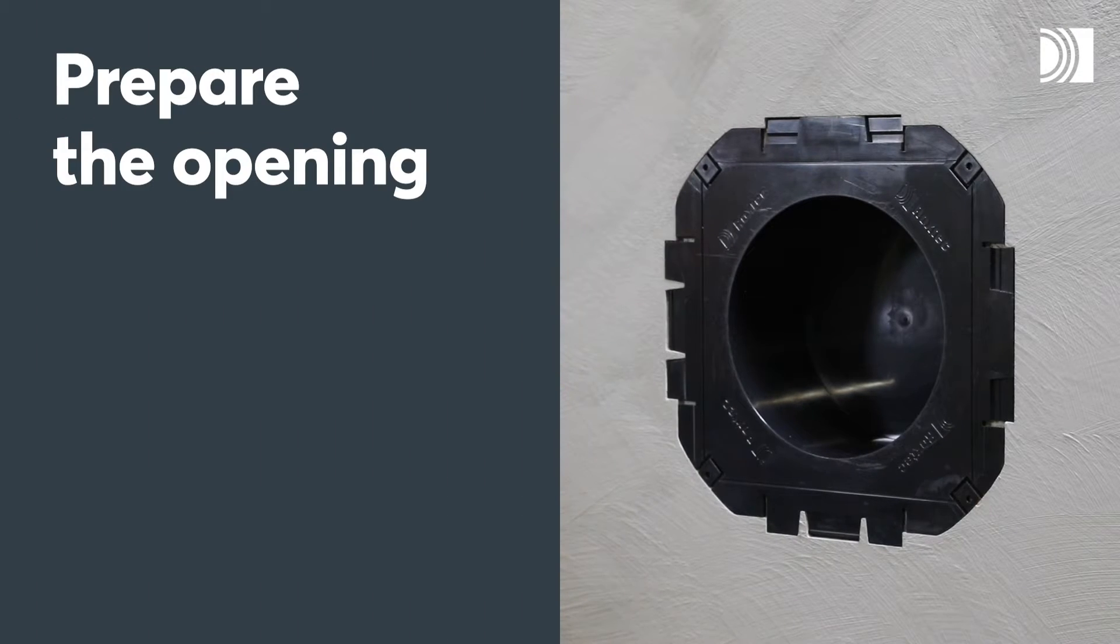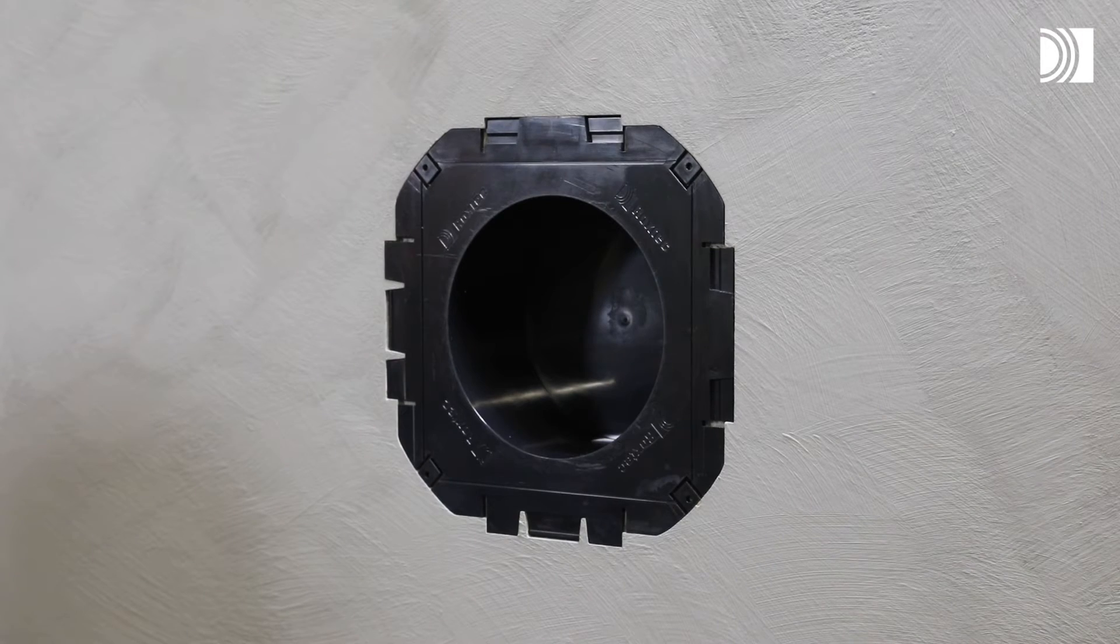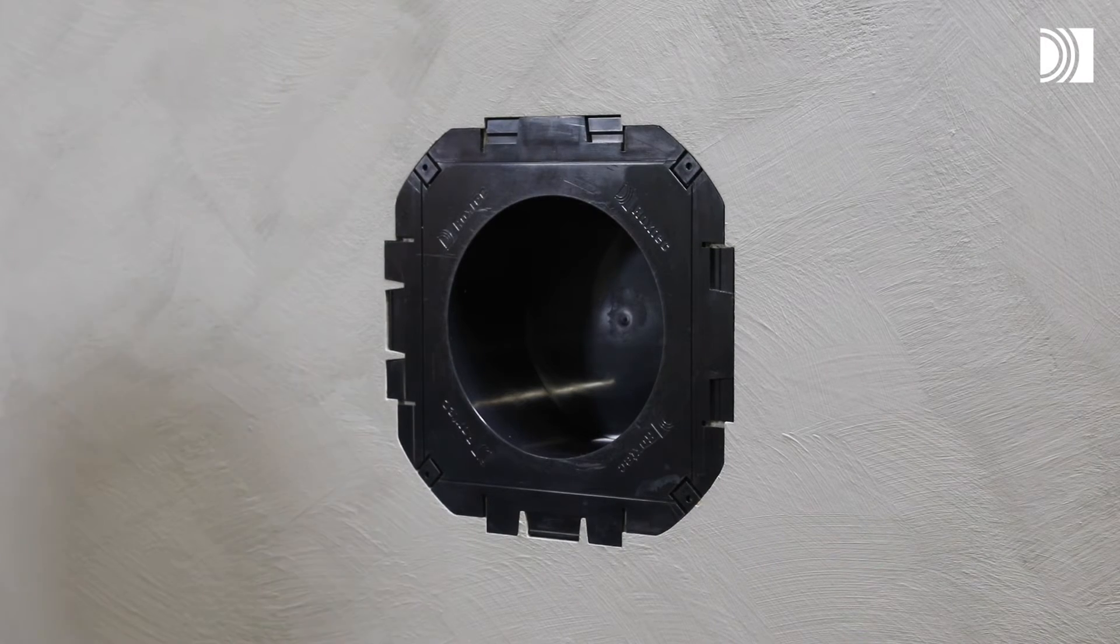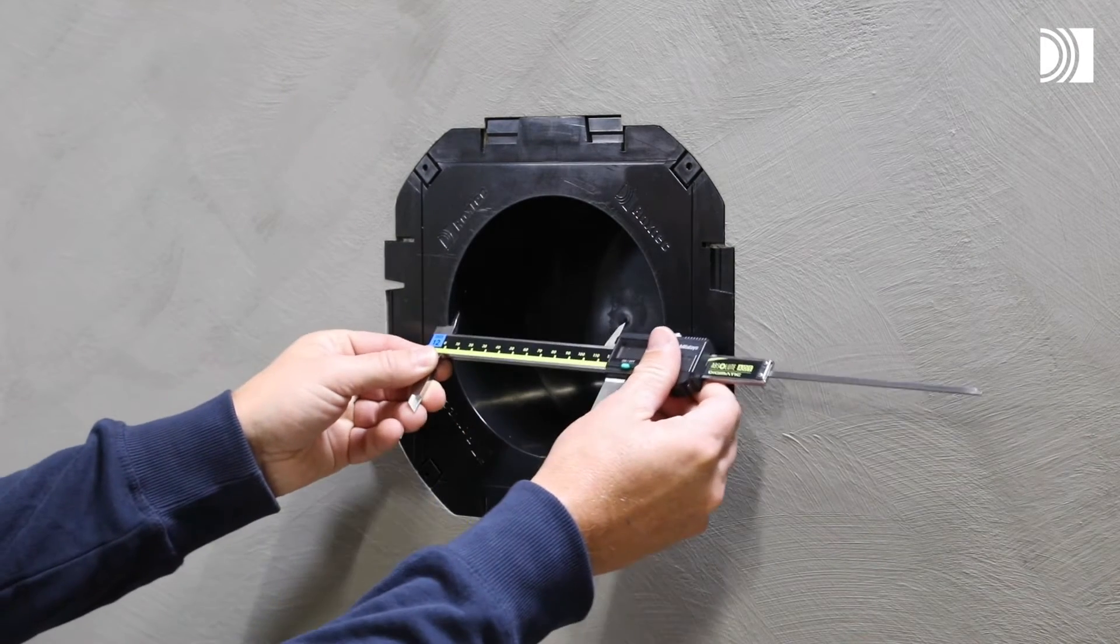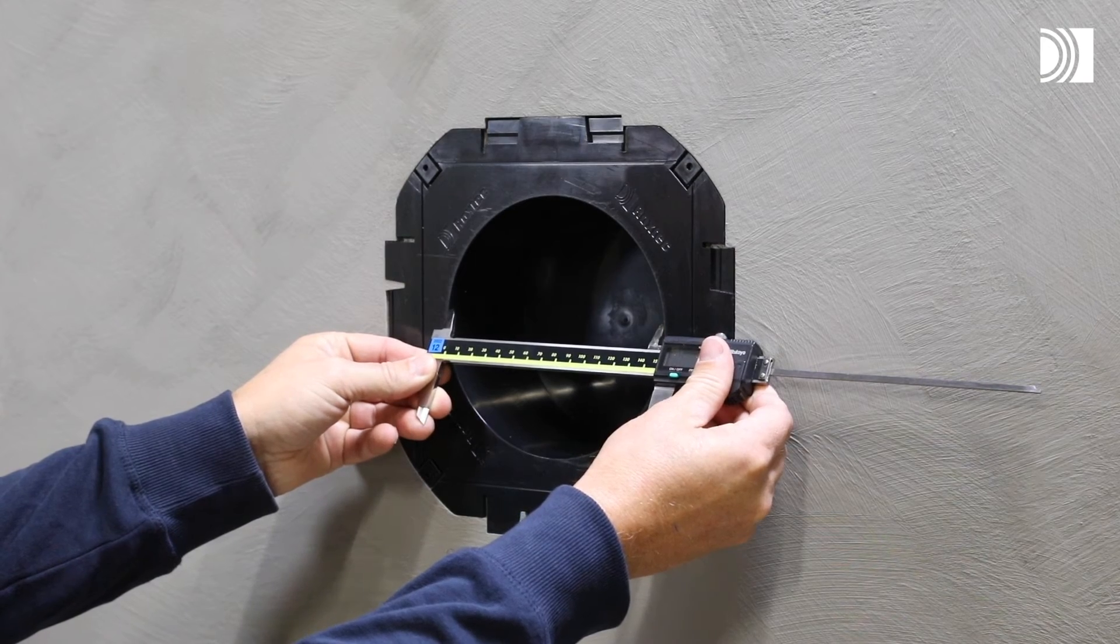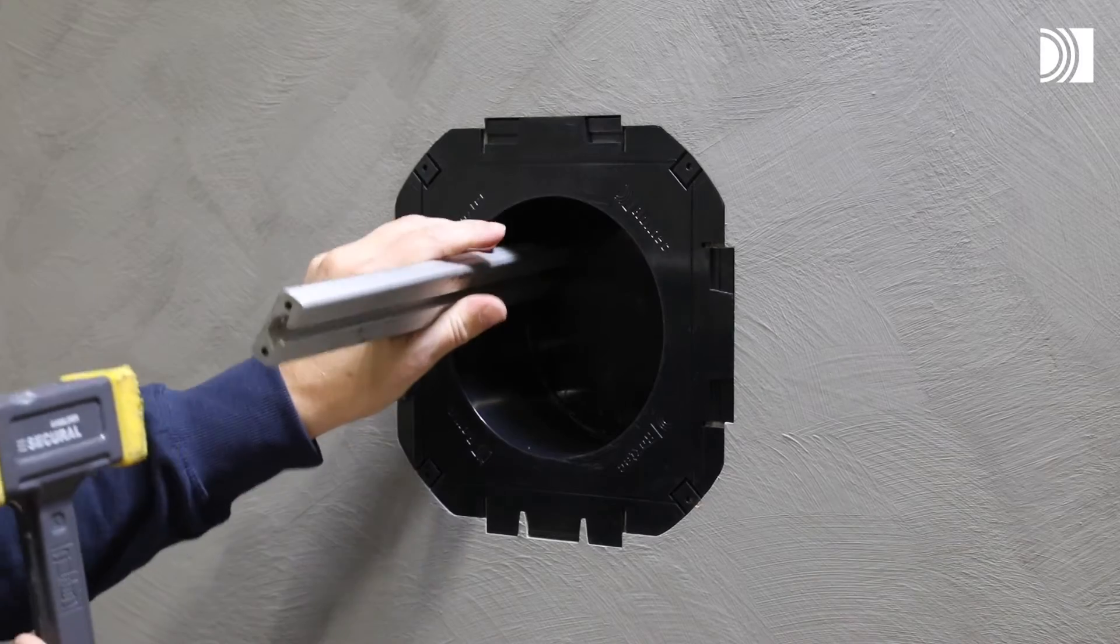Prepare the opening. In this case, the transit is installed in a Roxtec knockout sleeve. Start by verifying the aperture. Remove the knockout of the sleeve.